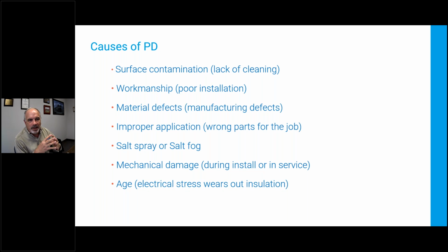So what causes PD? The number one cause is surface contamination. People don't clean their switchgear. Maybe they just get dust. Maybe they're in a salt environment. Maybe they're in a steel mill and they've got conductive dust. Maybe they're in an oil refinery, whatever. But you get the contamination on the switchgear. It doesn't get cleaned off. And maybe it's conductive, which would then obviously change our field distribution. If it is not conductive, it's still going to attract moisture in the form of humidity. So on humid days, it's going to become conductive. And so, that's why we clean switchgear, purely to prevent surface discharge.